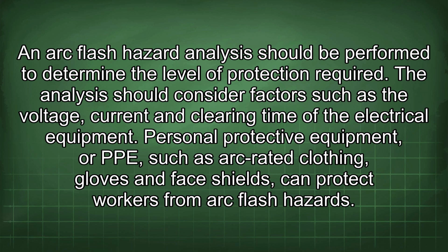An arc flash hazard analysis should be performed to determine the level of protection required. The analysis should consider factors such as the voltage, current, and clearing time of the electrical equipment. Personal protective equipment, or PPE, such as arc-rated clothing, gloves, and face shields, can protect workers from arc flash hazards.